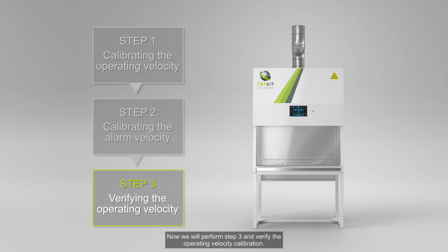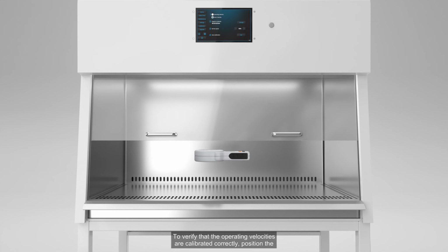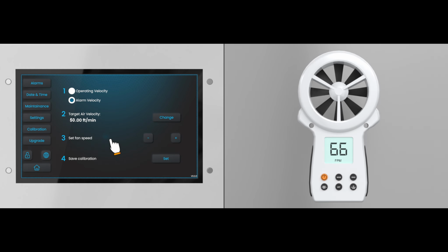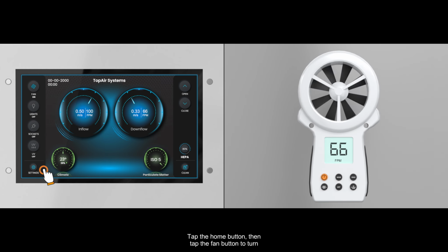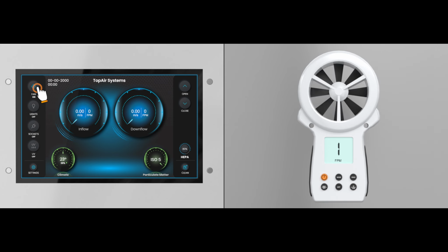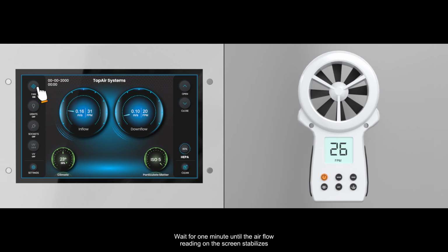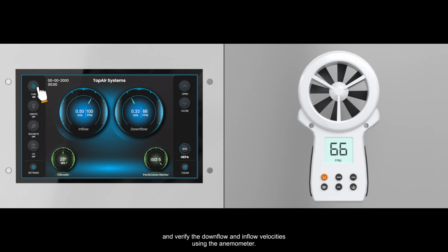Now we will perform Step 3 and verify the operating velocity calibration. To verify that the operating velocities are calibrated correctly, position the anemometer horizontally inside the cabinet, 12 inches above the work surface. Tap the Home button, then tap the Fan button to turn off the blower and tap it again to turn it back on. Wait for 1 minute until the airflow reading on the screen stabilizes and verify the downflow and inflow velocities using the anemometer.